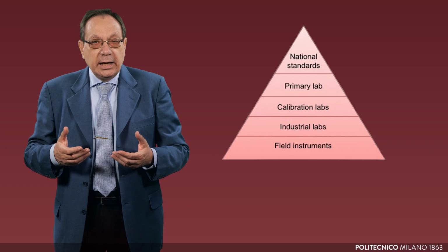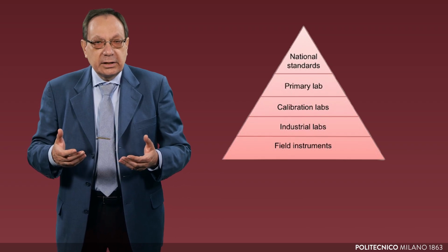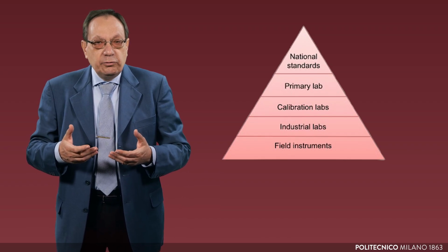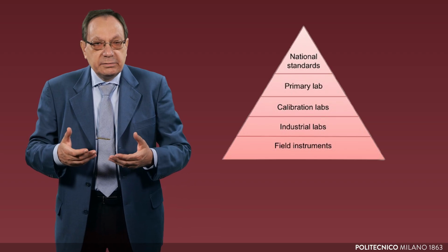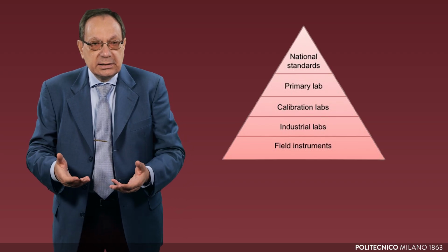institute. These instruments are used to calibrate the reference instruments of other calibration laboratories, which in turn are used to calibrate the reference instruments of industrial laboratories or other activities, for example in the clinical field. Finally, these latter instruments are used to calibrate the instruments employed in the field. In this way, a hierarchical pyramid structure is created in which each level transfers metrological traceability to the next level.